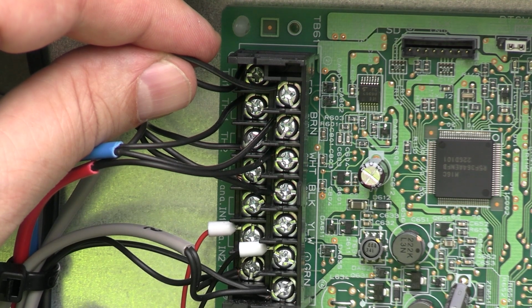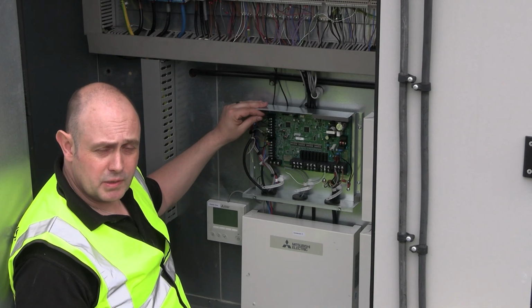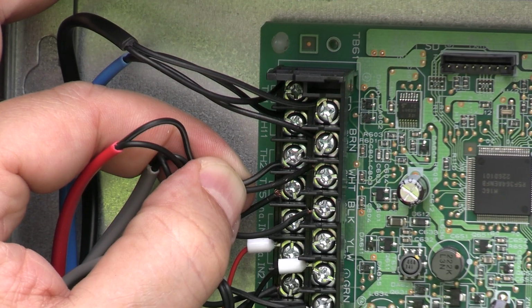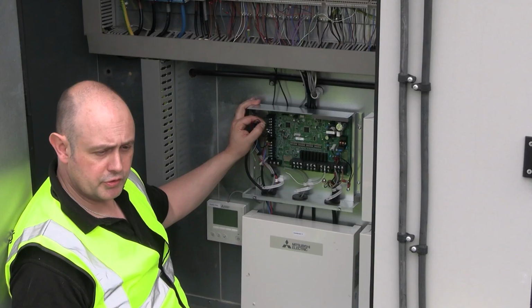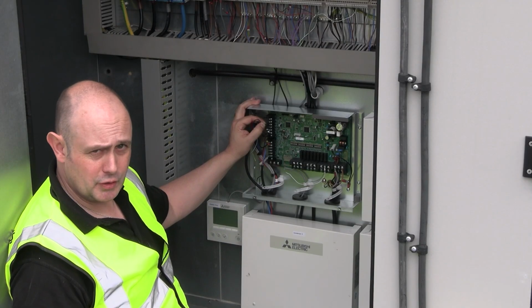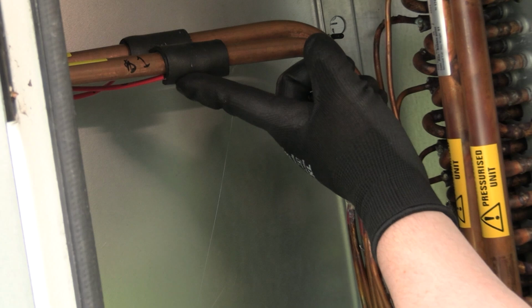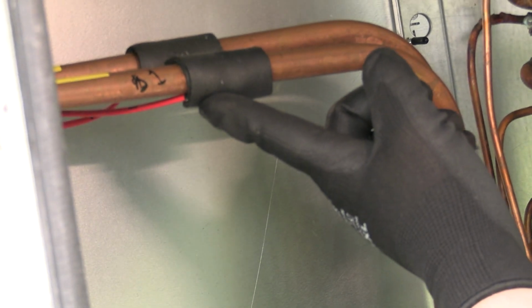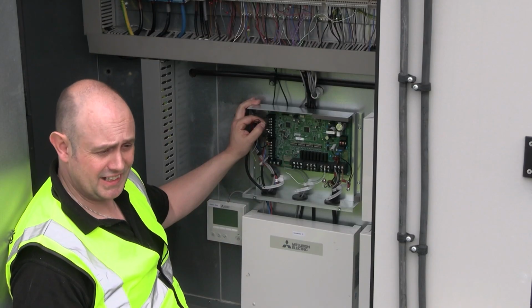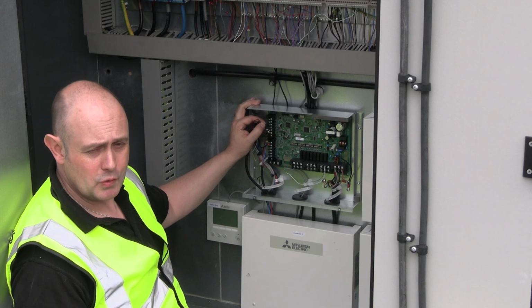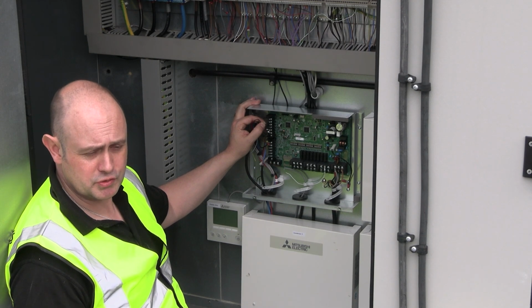TH1 connection on the board, and that's my target temperature, so that's what it's actually going to be targeting. So we've got TH2 here. That's measuring the temperature of the refrigerant as it's about to go into the coil. So it's marked down as being liquid line. We know this is actually a mix of liquid and vapor because the expansion valve is at the outdoor unit, but in theory, we're going to call that a liquid line. So that's where we're measuring that from.